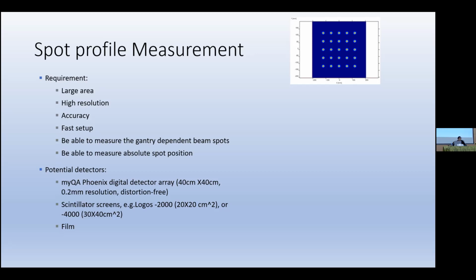But when you're measuring these things, you have to know what field size you have so you can measure the different points. Because the beam, as it comes down the center axis, depending again on how the system is designed, when it goes off to the corner, whether it's 20 by 20 or 30 by 40, whatever the field size is, that beam has slightly different characteristics. And if the system isn't well designed, and again, there are some systems that are not very well designed, the beam at the center is going to look great. The beam off to the corner is not going to look so good. It's going to get skewed. And depending on how skewed it is, maybe you can account for that in the treatment planning system, maybe you can't. So maybe they say they have a 25 by 25 field size, but the beam is so skewed out here in the corner, it's not usable. So then the usable field is 22 by 22.